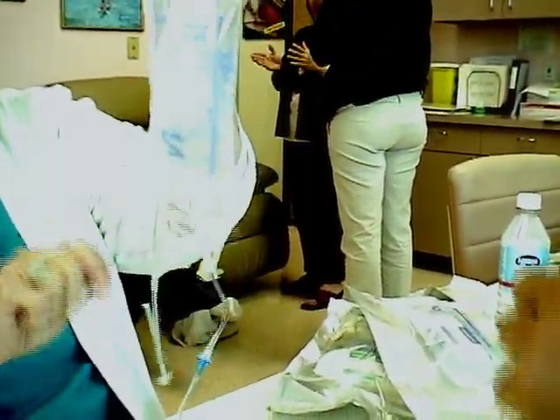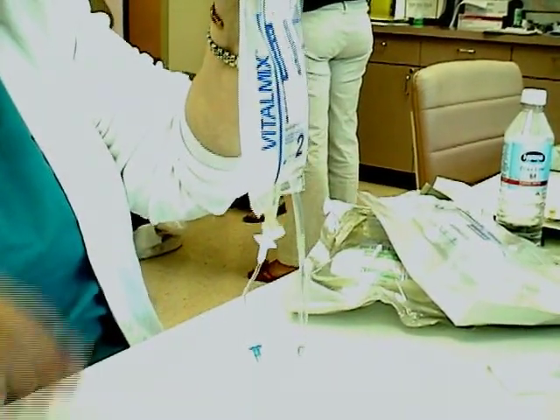Now take your hemostats off. Our procedure at that time was to get the largest amount of air out. We're still going to have bubbles in there, and we have these bubbles in the line, but they will be flushed as we continue to work on the bag. Now we're going to pick the bag up and tap all three ports this time. When you see no more air coming, we're going to lay the bag down parallel on the table with the clear side up.